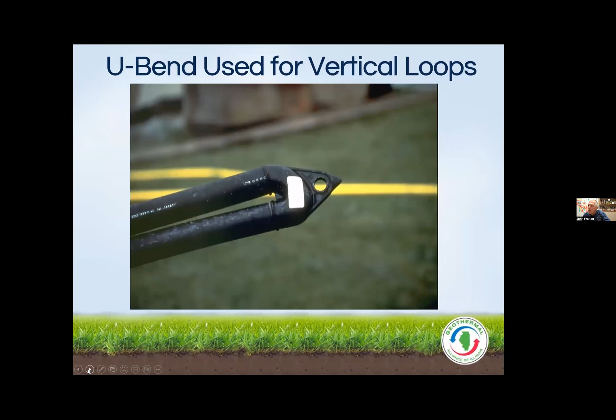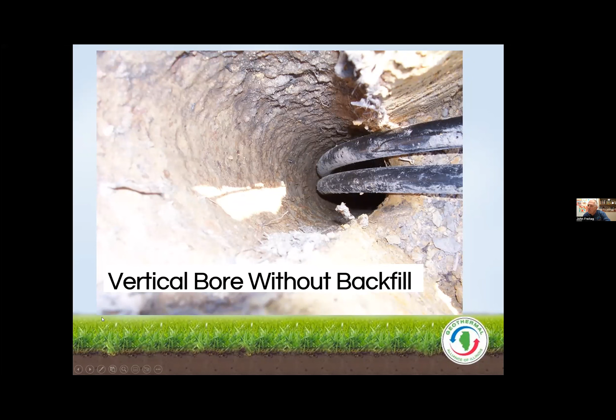This is what the piping looks like at the bottom of the borehole - a U-bend. This is what a borehole typically looks like. A real common one would be a 5-inch borehole drilled to the prescribed depth - mine in my front yard is 175 feet deep. When the drill hits the bottom of the prescribed depth, the piping is inserted into the borehole, and then typically right away that borehole is grouted with bentonite grout. And why is that important?